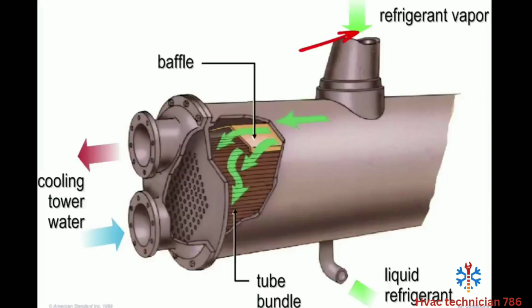The refrigerant leaving the third stage impeller will hit your volute, which is your discharge line that comes into your condenser. This superheated discharge gas will feed in and hit an upper baffle, which will distribute that gas across the condenser tubes. Your water is inside the tubes. This is a shell and tube heat exchanger, and your refrigerant is on the outside of the tubes. The superheated gas will stack in here in the top, and as the water flows through the tubes, it will begin to take in heat from that gas, and it will allow it to enter a state of saturation and eventually convert to a full liquid refrigerant.